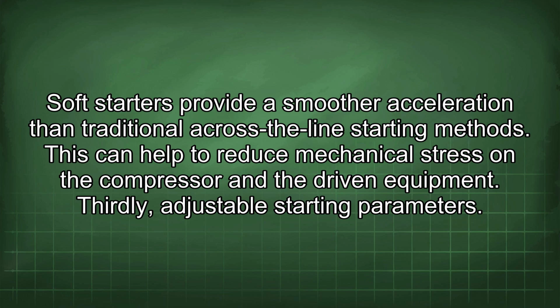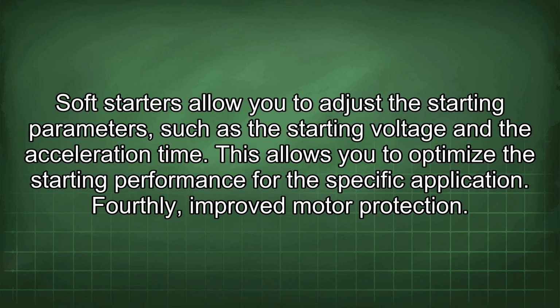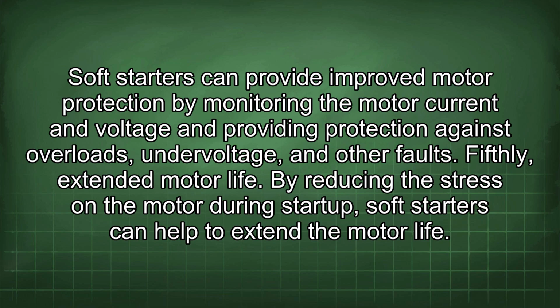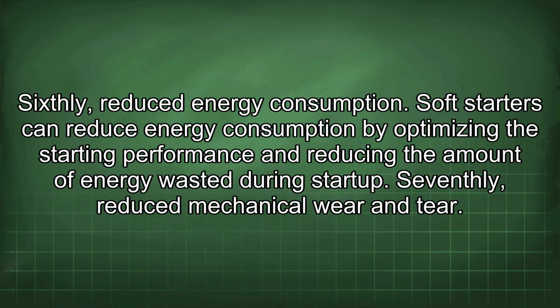Thirdly, adjustable starting parameters. Soft starters allow you to adjust the starting parameters, such as the starting voltage and the acceleration time. This allows you to optimize the starting performance for the specific application. Fourthly, improved motor protection. Soft starters can provide improved motor protection by monitoring the motor current and voltage and providing protection against overloads, undervoltage, and other faults. Fifthly, extended motor life. By reducing the stress on the motor during startup, soft starters can help to extend the motor life. Sixthly, reduced energy consumption.